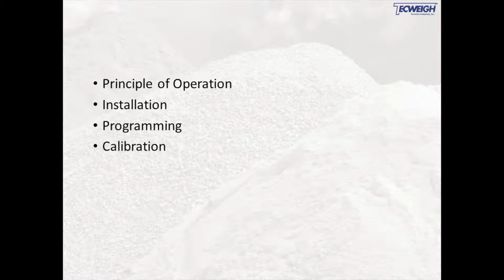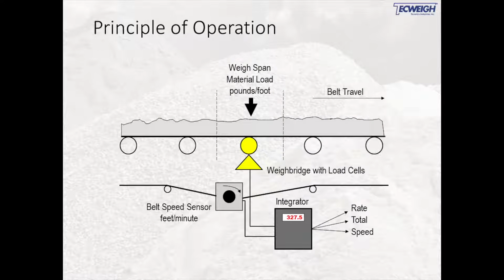In this video for belt scales, we're going to cover principle of operation, installation, programming, and calibration. Belt scales measure the weight of material or material load in an area called the weigh span. The scale processor continuously computes the rate of material by calculating the pounds per foot loading multiplied by the belt speed in feet per minute to equal the rate in tons per hour.